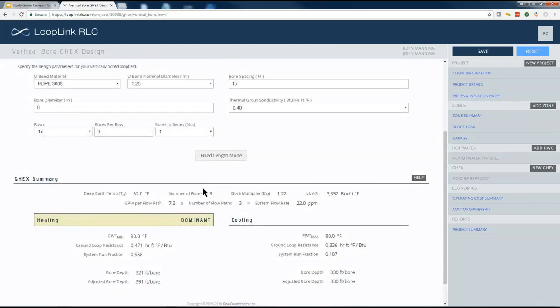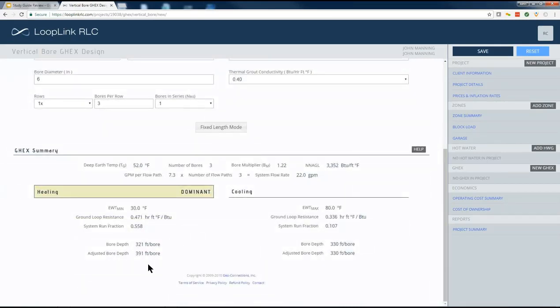So based on that, the way this system is designed right now, 3 bores, spaced 15 feet on center, with a 0.4 grout conductivity, you'd have to put in 3 bores, 391 feet, to maintain a 30-degree minimum EWT value in heating mode. Okay. So be very specific when you go to your drilling contractor. Don't go to them and tell them I want a 7-ton loop field. Go tell them I want 3 bores to 400 feet deep with this spacing and this grout. Be very specific about what you're asking for, right?